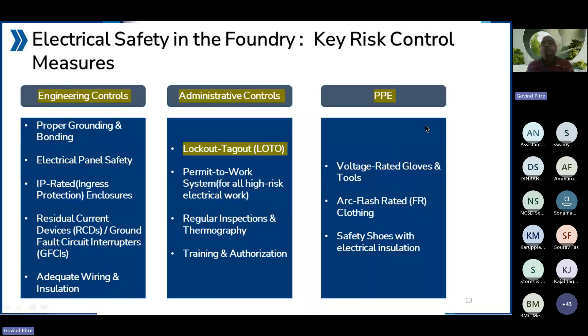Last one is personal protective equipment, where we need voltage rated gloves, arc flash rated clothing, and safety shoes with electrical insulation. Many companies we have seen do not conduct arc flash studies. Many people do thermography study, but arc flash study is conducted by very few people. But this is very useful to avoid serious incidents, not only in the LT panel area, but also the other resultant losses.